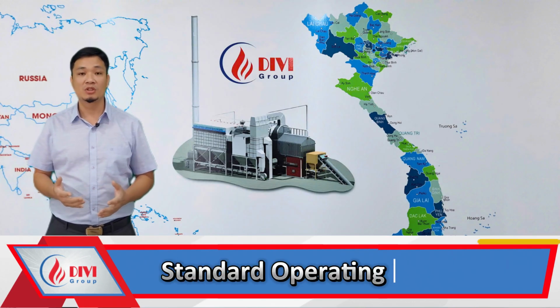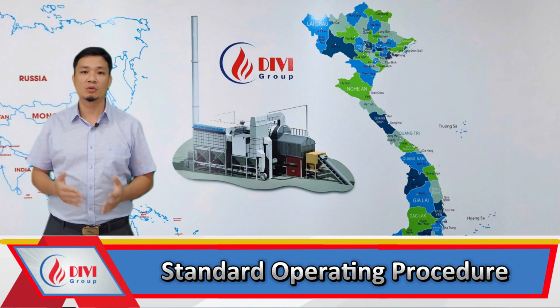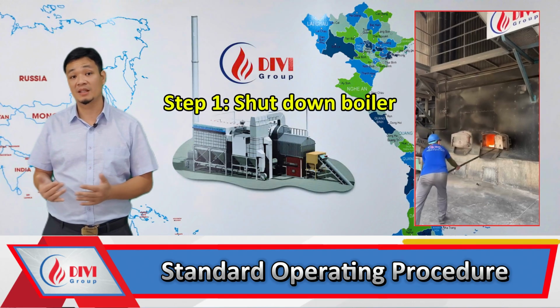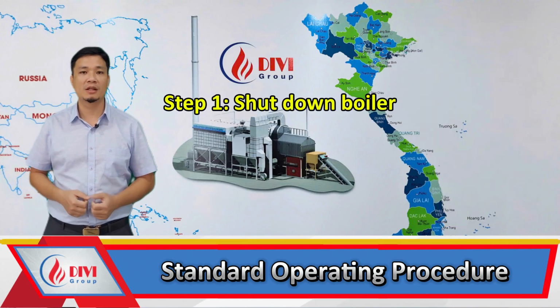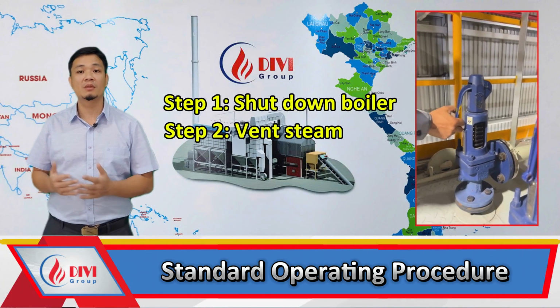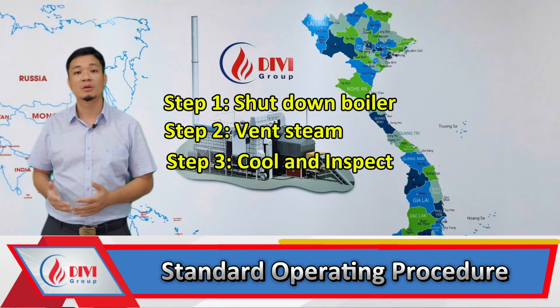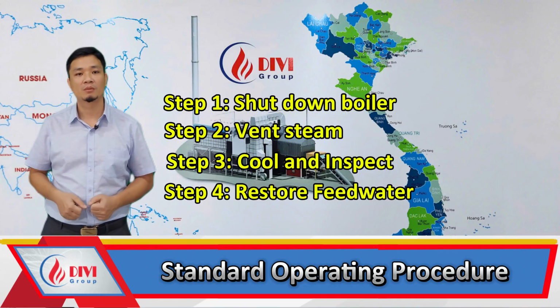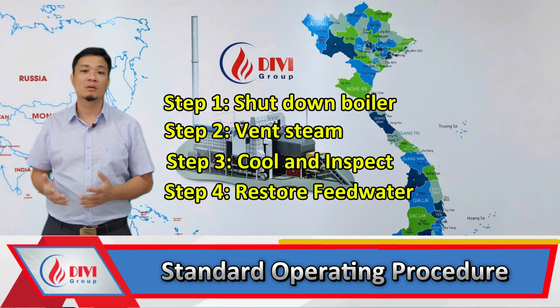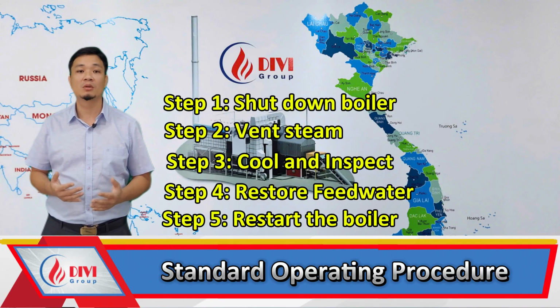Summary. Emergency dryout response workflow. Shut down the boiler. Isolate fuel and heat source. Vent steam to reduce internal pressure. Cool the boiler and inspect thoroughly. Refill manually, only after fault resolution. Restart with full adherence to SOP.